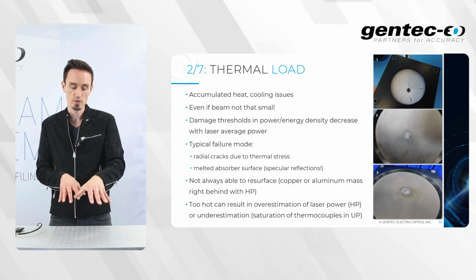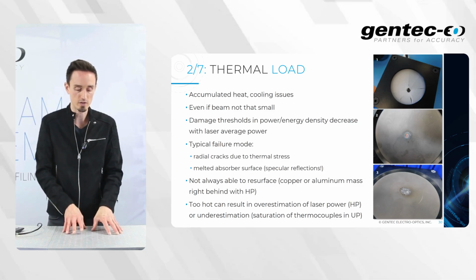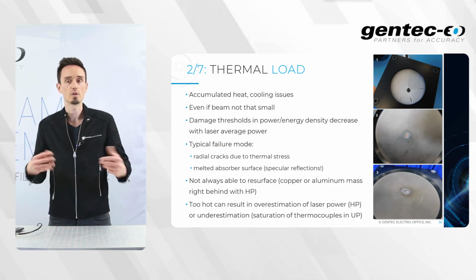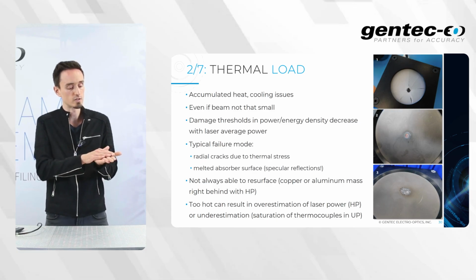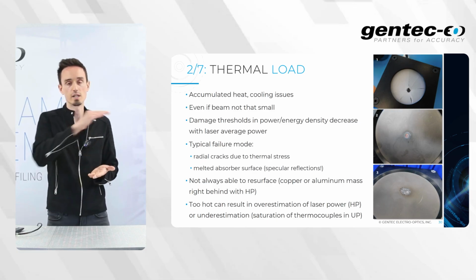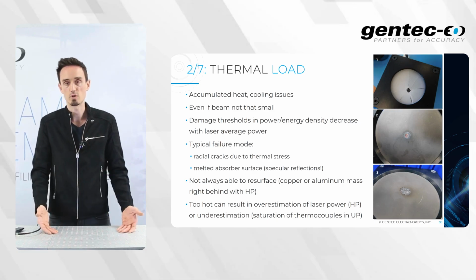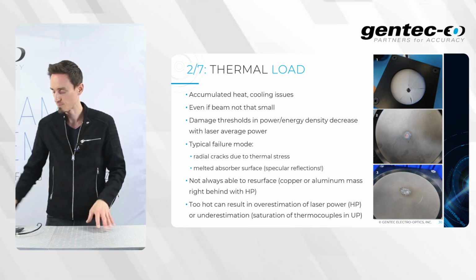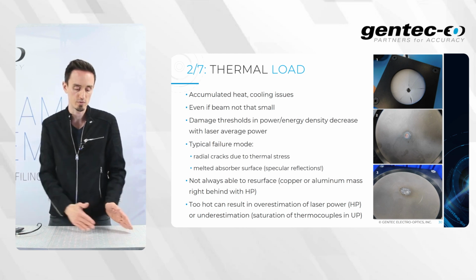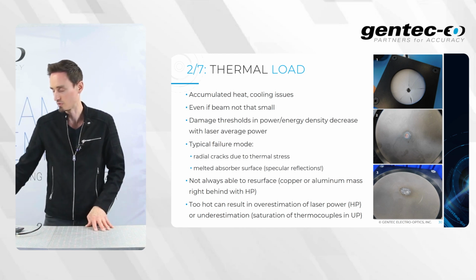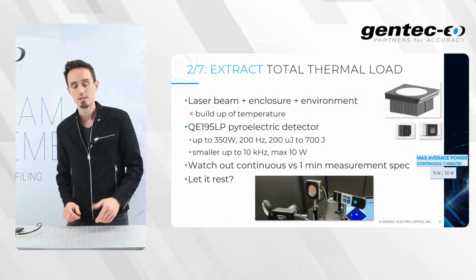And if it's for using thermocouple-based UP detectors, if it is too hot, you will get to a regime where the thermocouple response gets saturated. So the measurement will be underestimated in this case. It's good to know those kinds of defects because it will help to anticipate what you could see in the field if you have those situations.